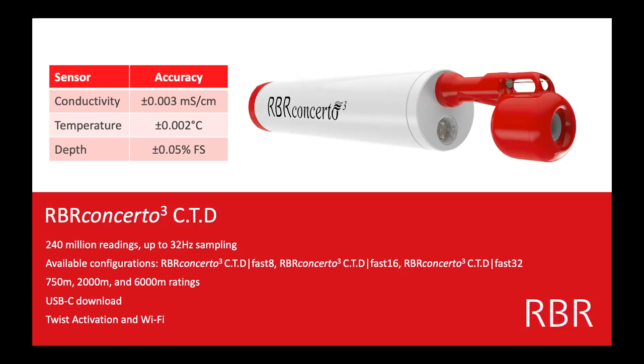This particular instrument can take 240 million readings. You can sample really quickly, up to 32 hertz. We have lots of different variations — fast sampling, deep sampling. This particular one here has plastic housing, so this unit can go to 750 meters. If you go beyond that, we recommend titanium housing. Eric's instruments are titanium and they can go to 2,000, actually up to 6,000 meters.